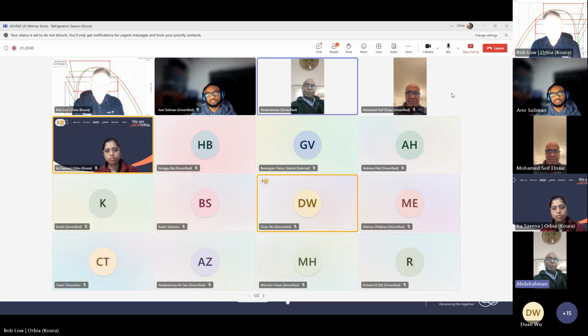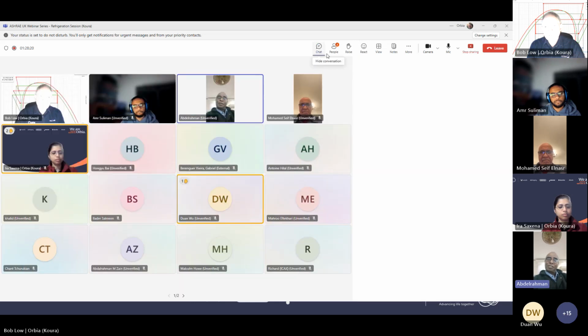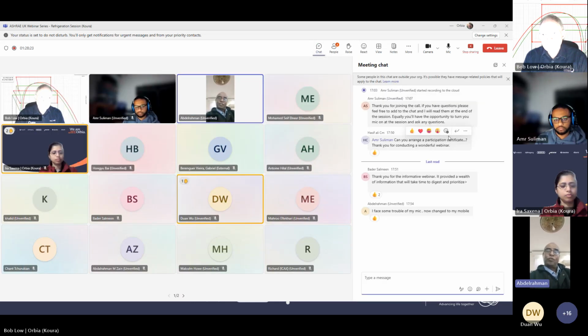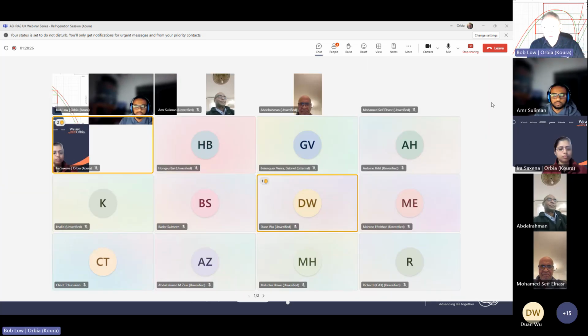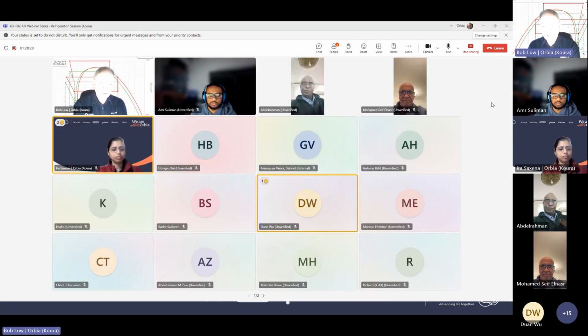Yes, but for R32, there are many problems concerning lubrication, solubility, and the ignition level, also for safety. Yeah. Because you cannot charge a big capacity unit with this type of refrigerant, only a small unit. Yes. The charge size limits in EN 378, for a single split system, you're looking at about 4 to 5 kilos of R32. So that's, in American parlance, about a 3-ton unit, 9 kilowatts.